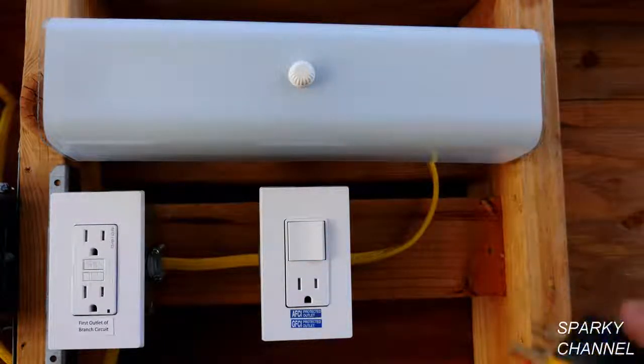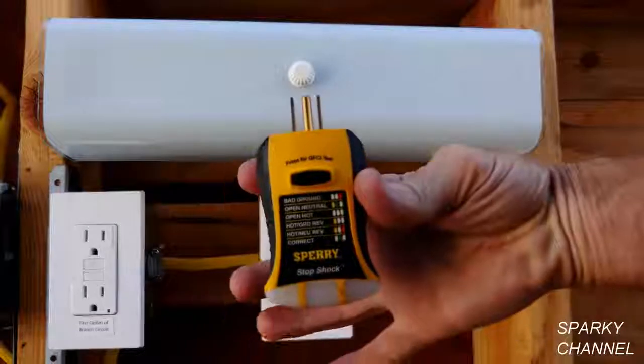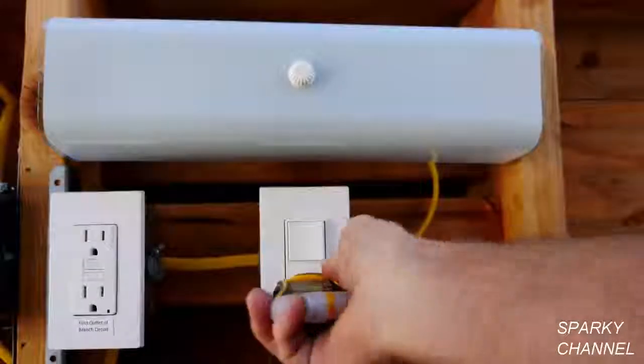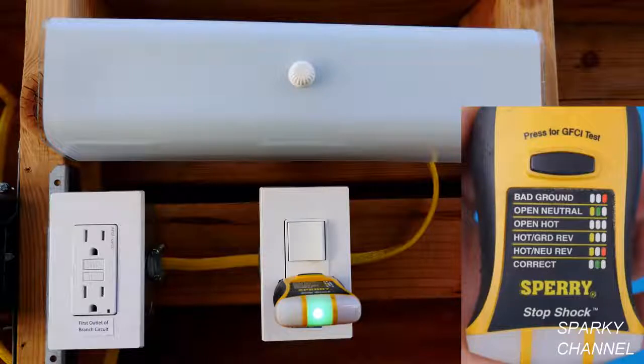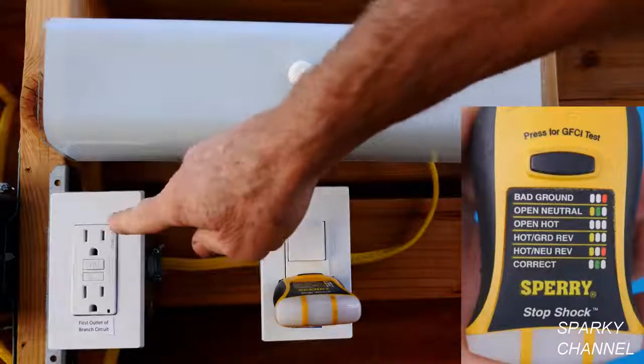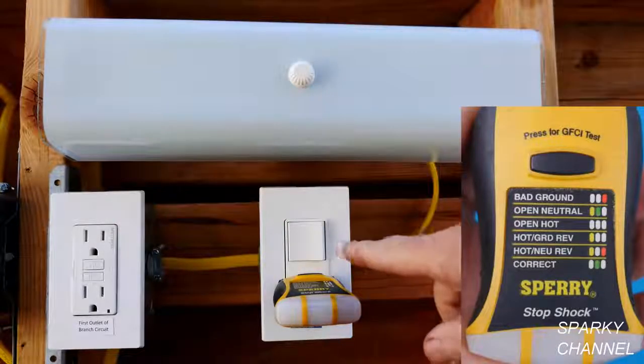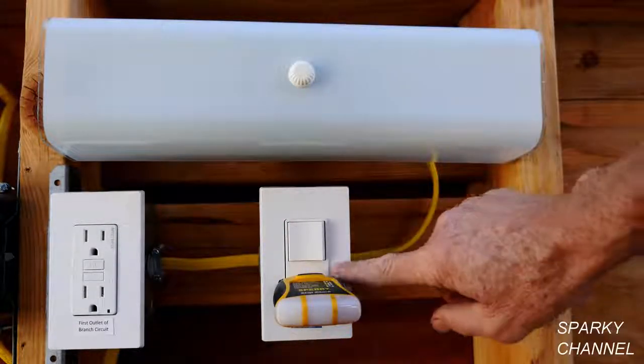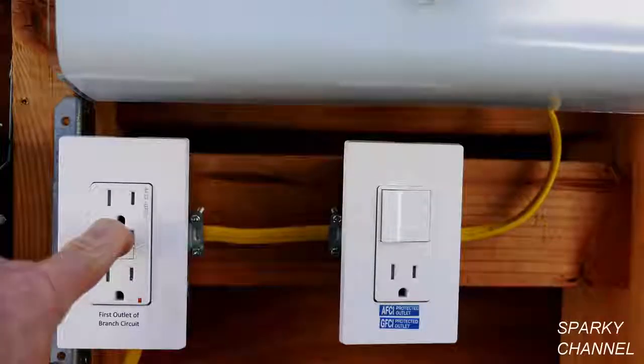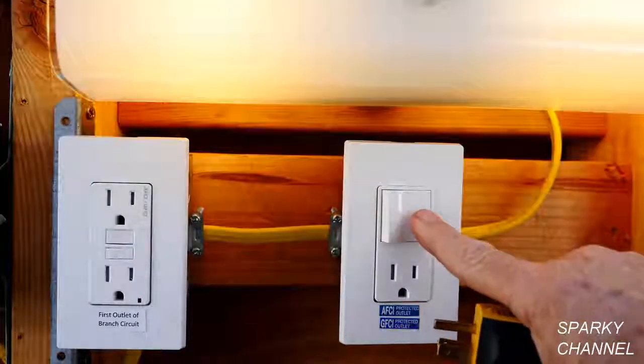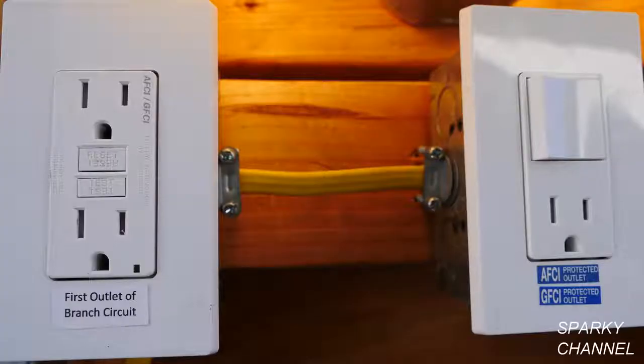Okay, now we'll test out the receptacle. This is my Sperry Stop Shock receptacle tester. You plug it in, and it gets one green light, which is proper. And we press test, and it goes out. So the AFCI, GFCI controls this receptacle properly. Also, the AFCI, GFCI receptacle protects the switch and light. So our combination switch and tamper resistant receptacle has earned its AFCI protected outlet and GFCI protected outlet stickers.